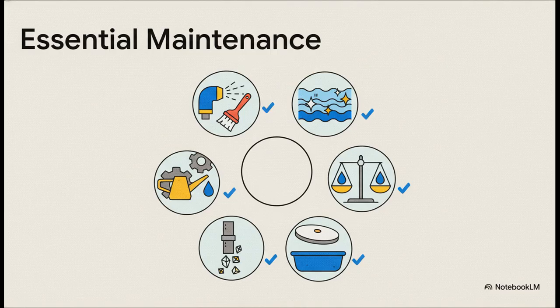For instance, cleaning your spray nozzles isn't just about cleaning, it's about making sure the water is spread evenly over the fill, which is totally critical for performance. And optimizing your blowdown rate, that's a constant balancing act between keeping mineral buildup in check and not wasting a ton of water and expensive chemicals.